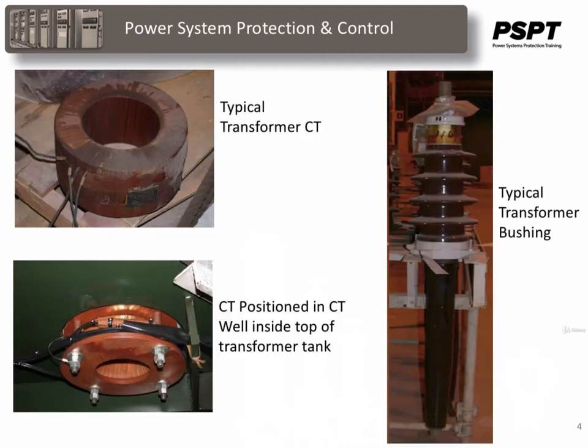These are examples of CTs or current transformers that are found in a power transformer. They are known as donut CTs for their similar look to a donut. The picture on the right is not a CT, but a typical transformer bushing, which would be mounted through the center of a donut CT.